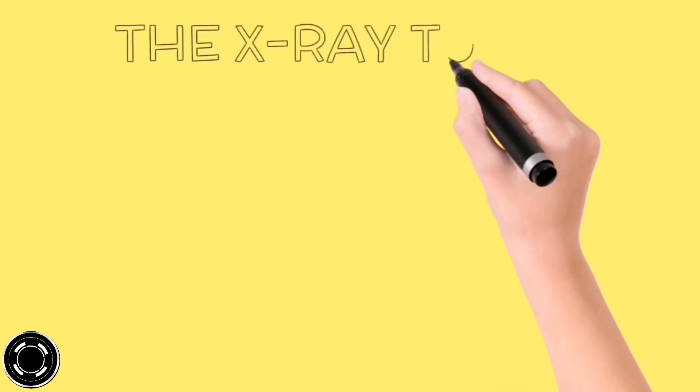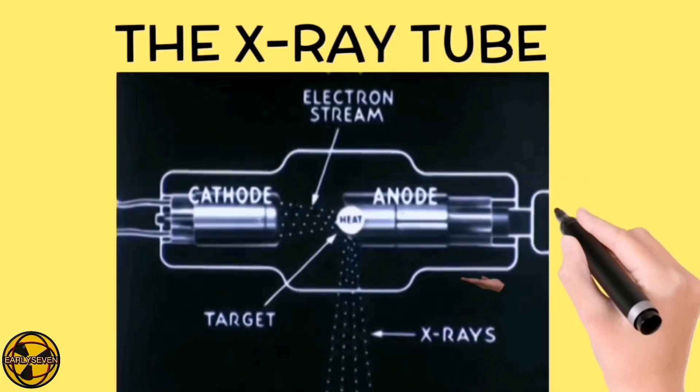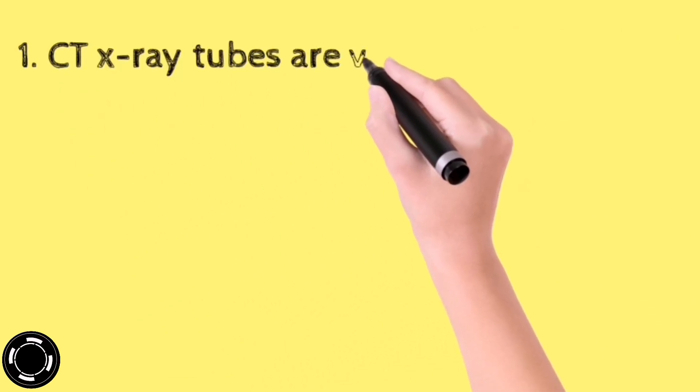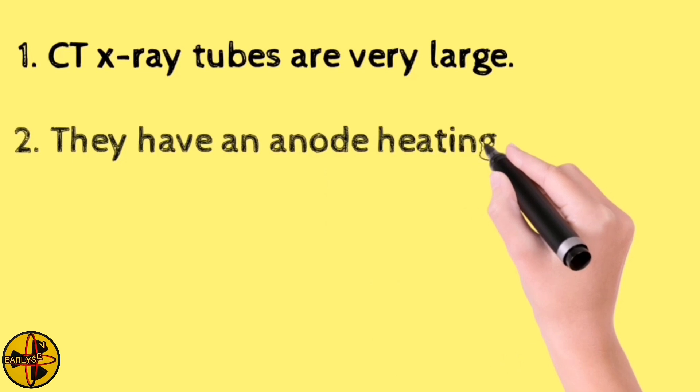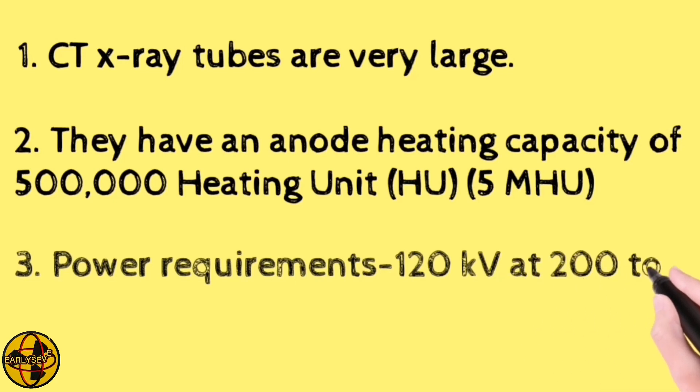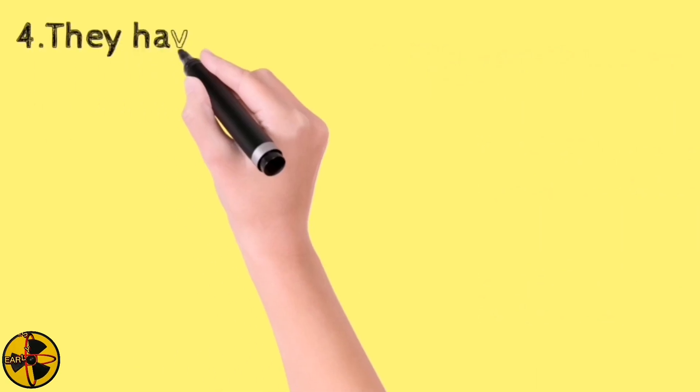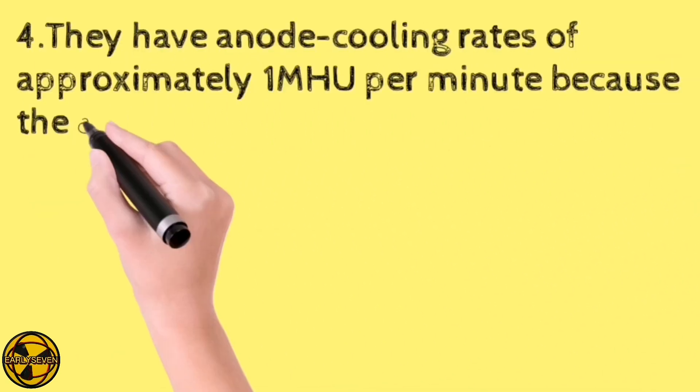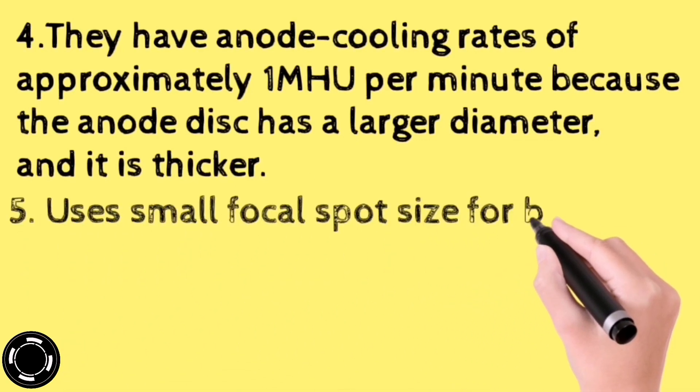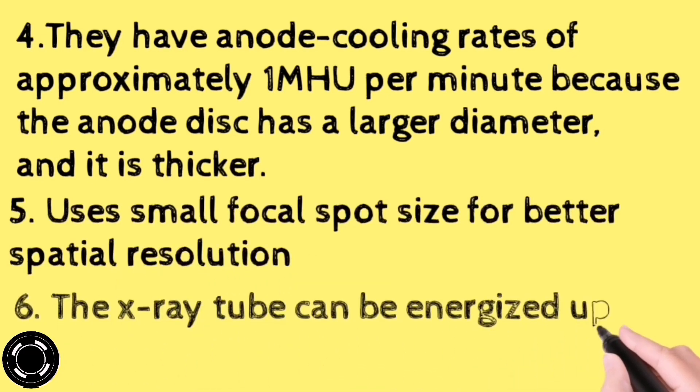The next component of computed tomography or a CT scanner is the x-ray tube. The CT scan x-ray tubes are very large. They have an anode heating capacity of 500,000 heating units. The power requirements for a CT scanner is 120 kV at 200 to 500 milliampere. They have an anode cooling rates of approximately 1 mhu per minute, because the anode disk has a larger diameter and it is thicker. It uses a small focal spot size for better spatial resolution. The x-ray tube can be energized up to 60 seconds.